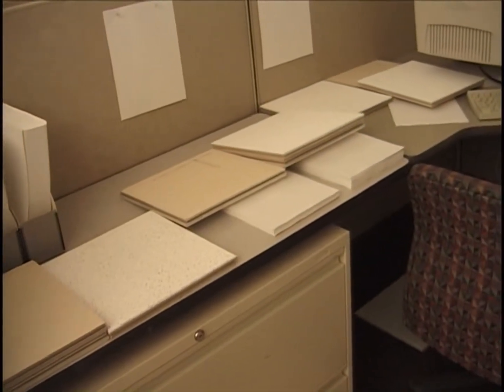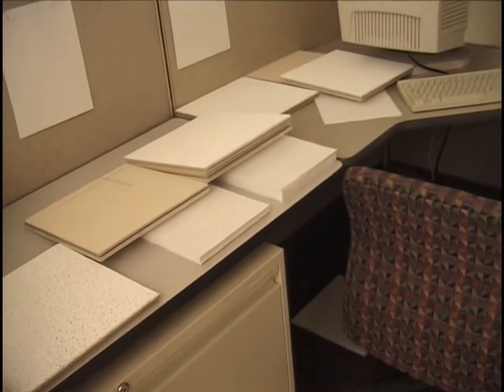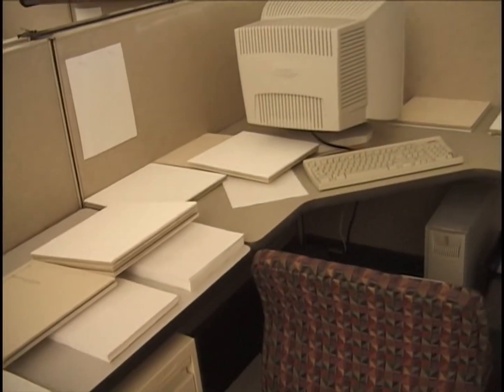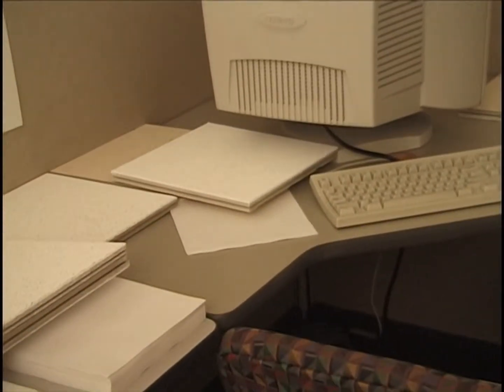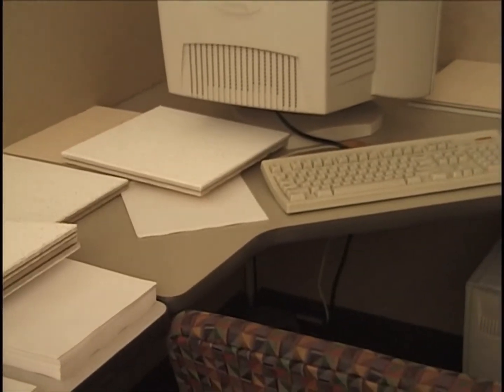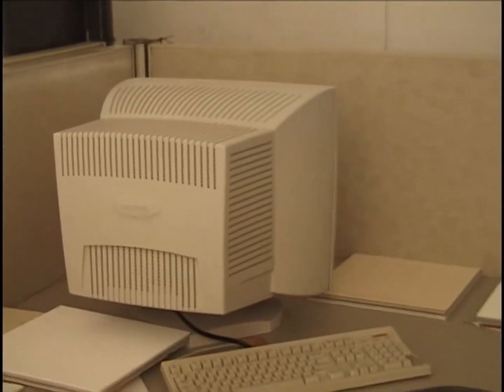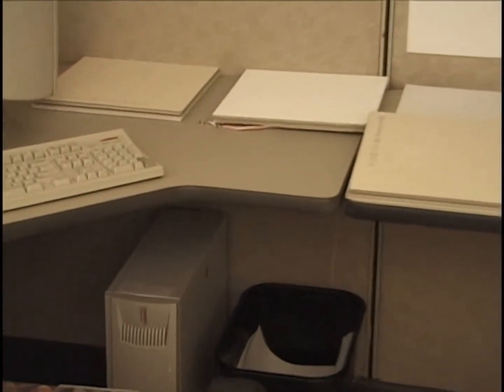So there's tiles placed on top of the paper piles. And notice that the tile placed where it is on top of the paper that normally ignites the computer is going to block that process, so only the keyboard has a chance to act as a pilot for the computer. There's a thermocouple on top of the desk, a thermocouple underneath, as usual.